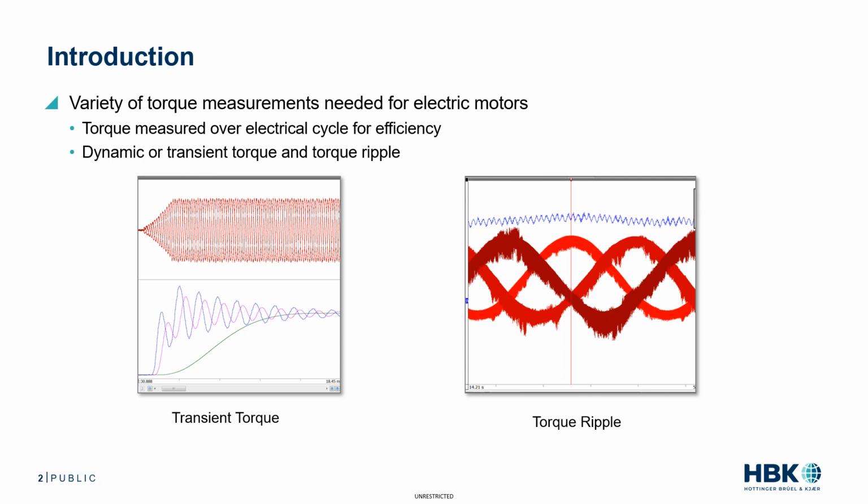When calculating efficiency, the parameters used to make the efficiency calculation, input power and output power, should be calculated over the same time period. Therefore, mechanical power and electrical power should be synchronous, calculated over the same time period. In Perception, that is done by calculating both quantities using the same cycle master.